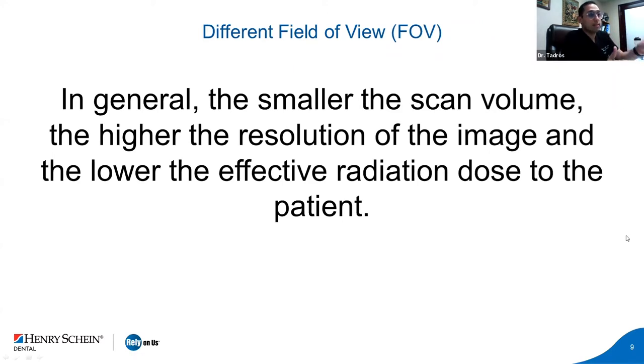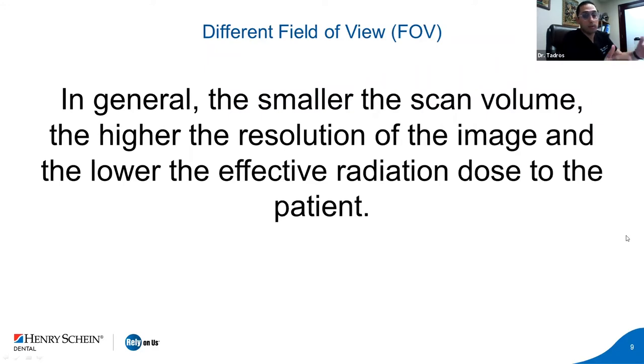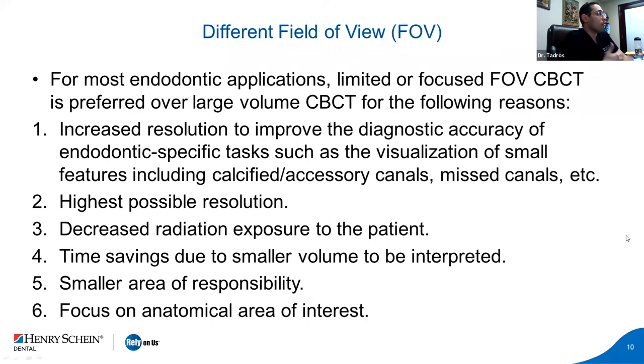In general, the smaller the scan, the smaller the view, the higher the resolution, and the lower the effective radiation dose. So if you want to image a small structure, you want to have a smaller field of view and smaller scan volume — you'll get higher resolution and lower radiation compared to a bigger field. That's what takes me to why and how we use CBCT in endodontics. For endo, a limited or focused FOV of CBCT is definitely preferred over large volume. For endo, you are focusing on one or two teeth and looking at anatomical areas around one particular area, so you don't really need a big field.